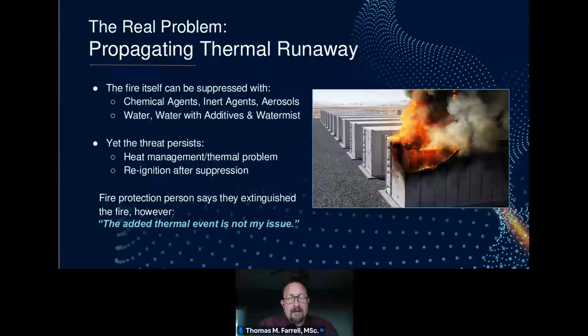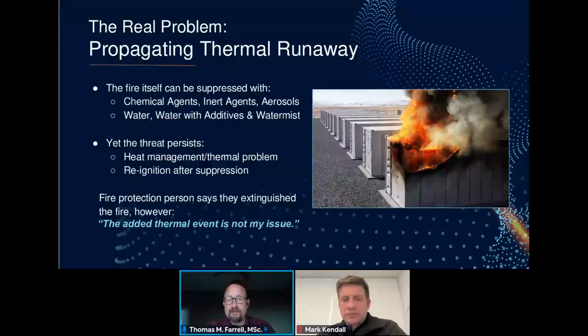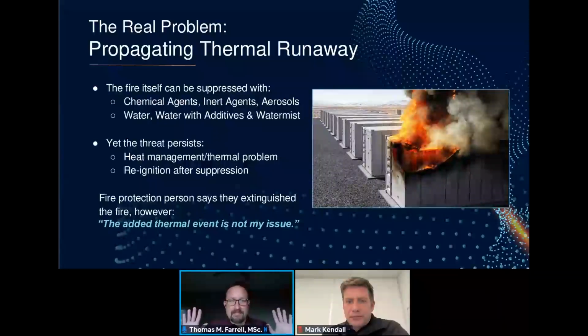That reignition then becomes a problem when you can have fires that burn for days on end. One of the big issues right now is that on a lot of protective system installations, the fire protection professional responsible for the system will say, yeah, we extinguished the fire, our system is a fire extinguishing system. The added thermal threat and thermal event that comes along with thermal runaway, that's not my problem.